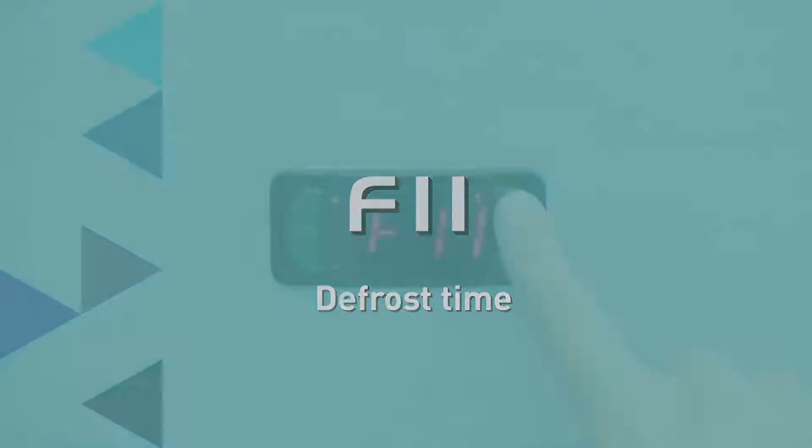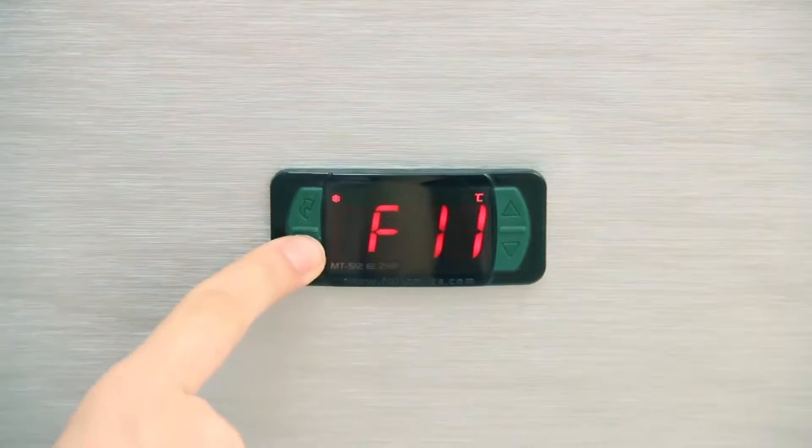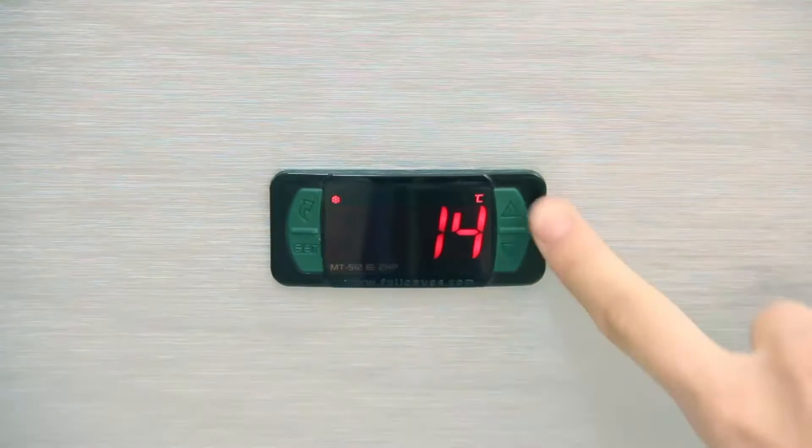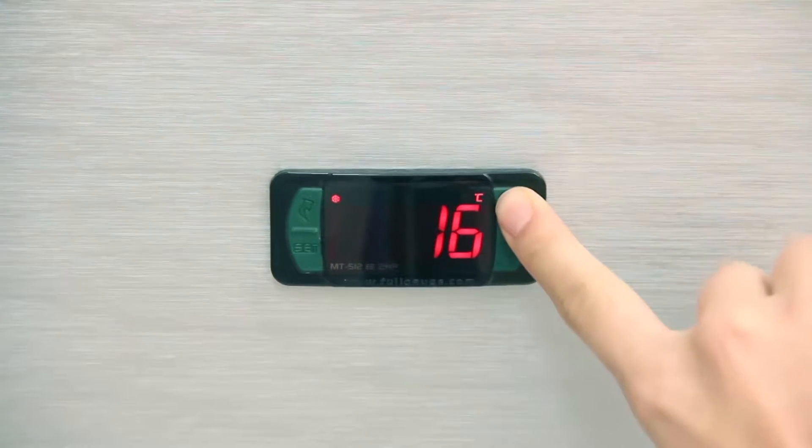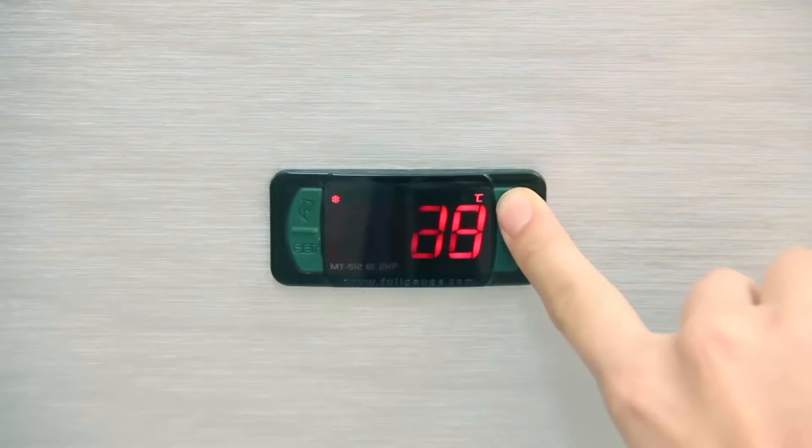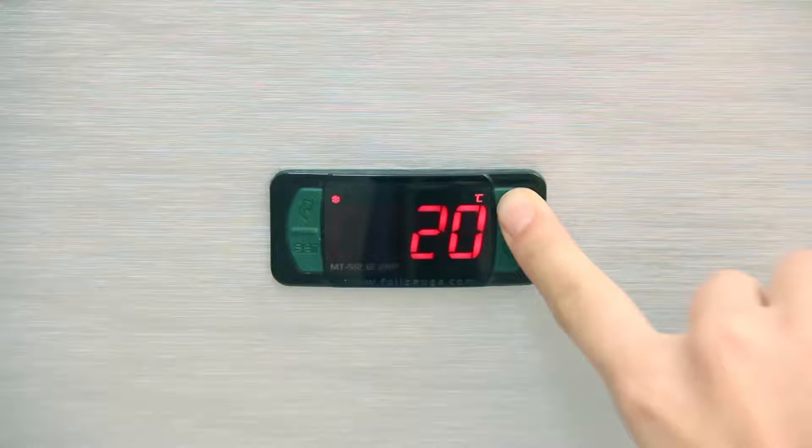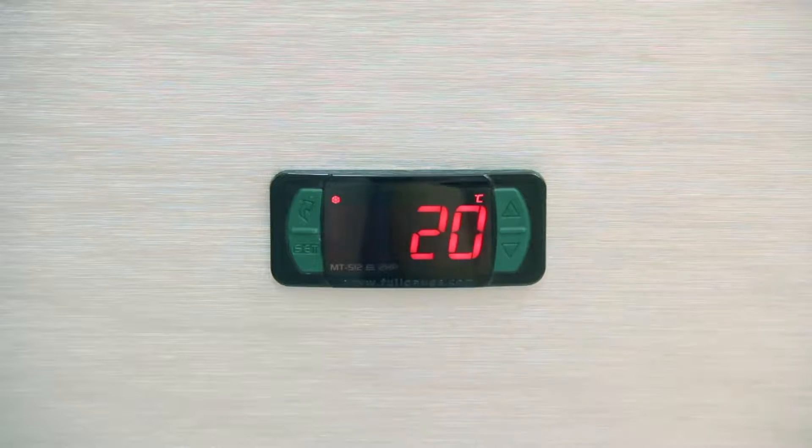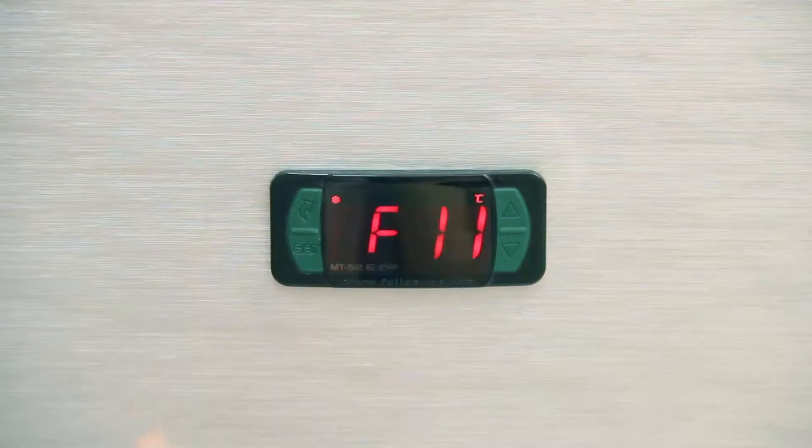F11, Defrost Time. It determines the minimum duration of the defrost time, that is, the time between cooling cycles. Select No, so as not to adopt a minimum time, or provide a value between 1 and 999 minutes. In this example, we determined a time of 20 minutes.